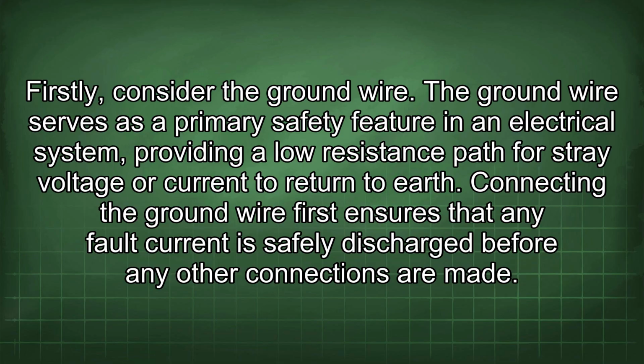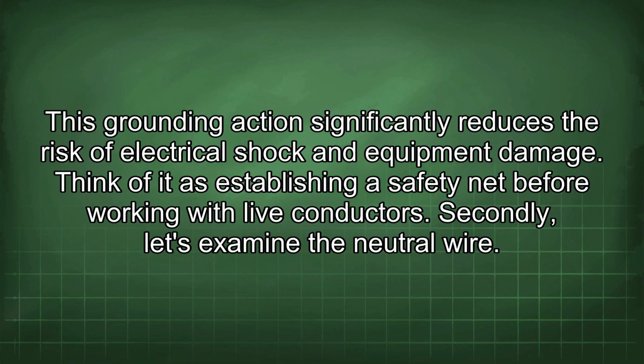Firstly, consider the ground wire. The ground wire serves as a primary safety feature in an electrical system, providing a low resistance path for stray voltage or current to return to earth. Connecting the ground wire first ensures that any fault current is safely discharged before any other connections are made. This grounding action significantly reduces the risk of electrical shock and equipment damage. Think of it as establishing a safety net before working with live conductors.